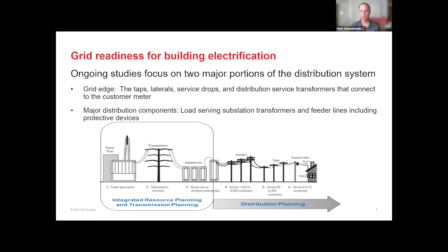So if we fully electrify, we're going to have costs basically at that service line. If a transformer, as shown in the picture here, serves anywhere from 4 to 10 customers, and you have one fully electrify their heat, it probably doesn't need an upgrade on the transformer. If you have 2, 3, 4, or 5 maybe on the same transformer, it will. So there will be upgrades required further up the distribution path, and we'll do it, right? That's part of being a regulated utility: we will provide service for customers.